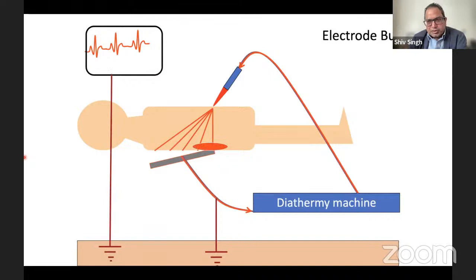Now, what if the patient was also connected to monitoring equipment which is earthed? In that case, the current can flow not only through the point of attachment, or if it is completely detached and there is no warning system, the current can flow to the electrode system, and that's how electrode burns used to occur. We don't see them now. But if you look at the literature, you will find patients with plate burns, and probably patients with electrode burns. These were common when the diathermy just had earth, so the plate was earth. So people realized that earth was dangerous.